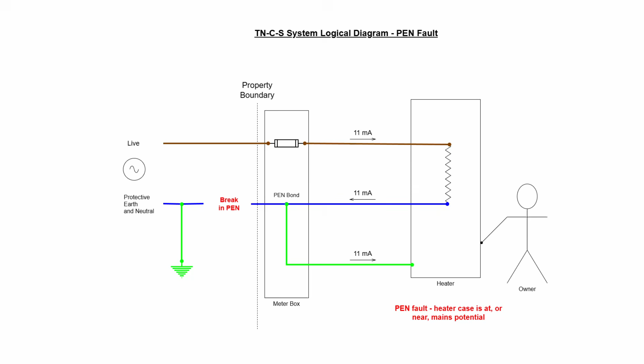Unfortunately, in a PEN fault, the current path is out along the live and back along the neutral before then running along the CPC. It's this unusual current path that means RCDs and GFCIs do not trip. The current on live and neutral is perfectly balanced, so they see no fault condition and can't help us. Other people asked if surge protectors or SPDs help in this situation. They are intended to clamp short, transient spikes in the incoming waveform, and that's not what our fault is, so they don't help either.